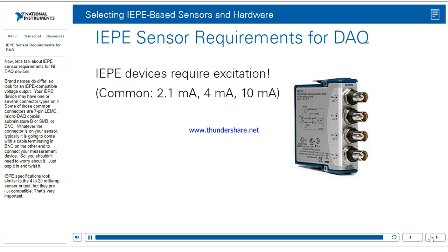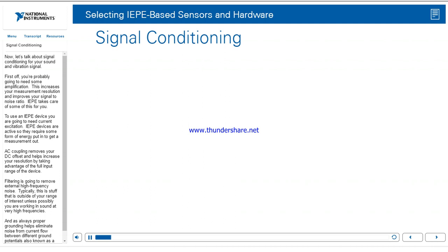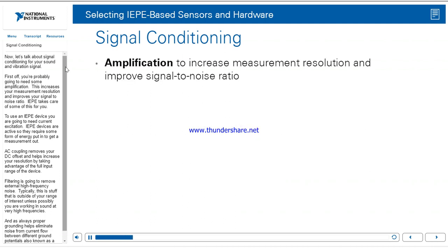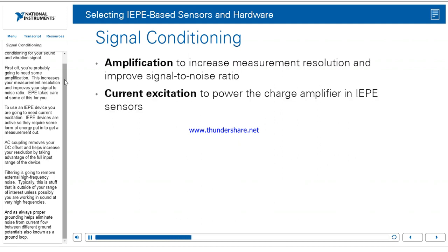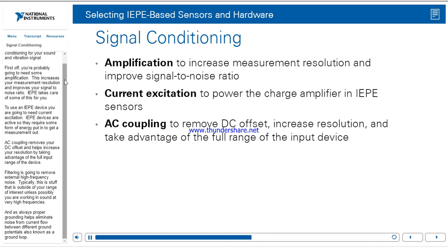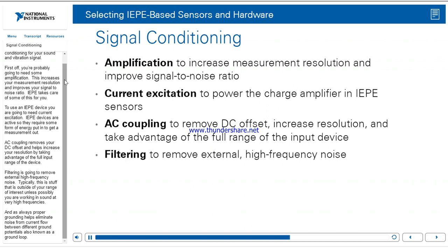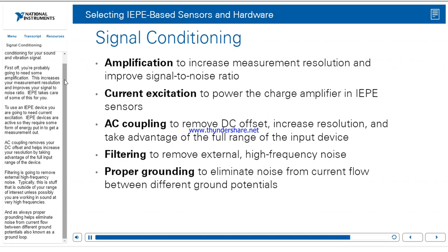Now let's talk about signal conditioning for your sound and vibration signal. First, you're probably going to need some amplification — this increases your measurement resolution and improves your signal-to-noise ratio, and IEPE takes care of some of this for you. To use an IEPE device, you're going to need current excitation, as IEPE devices are active and require energy input to get a measurement out. AC coupling removes your DC offset and helps increase your resolution by taking advantage of the full input range of the device. Filtering removes external high-frequency noise, typically outside your range of interest. And as always, proper grounding helps eliminate noise from current flow between different ground potentials, also known as a ground loop.